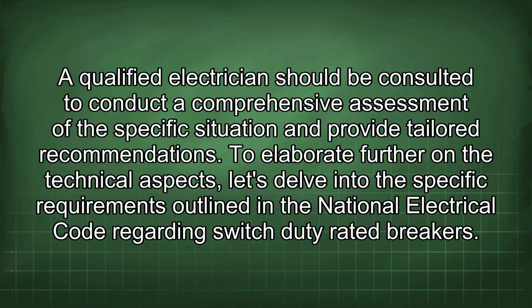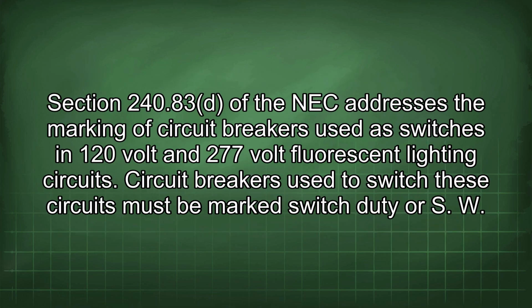To elaborate further on the technical aspects, let's delve into the specific requirements outlined in the National Electrical Code regarding switch duty rated breakers. Section 240.83 of the NEC addresses the marking of circuit breakers used as switches in 120 volt and 277 volt fluorescent lighting circuits. Circuit breakers used to switch these circuits must be marked switch duty or SWD.